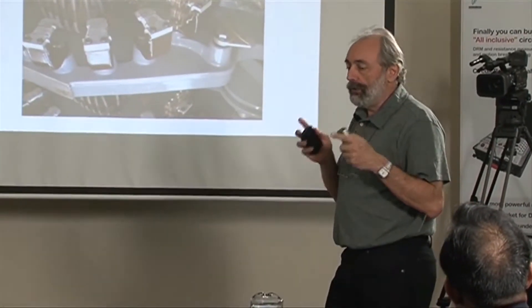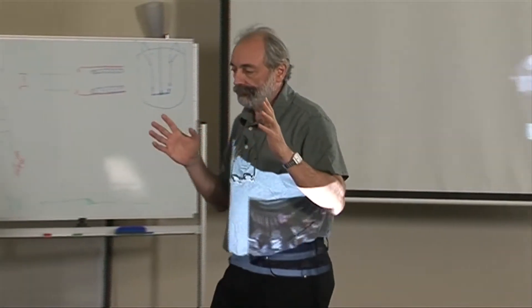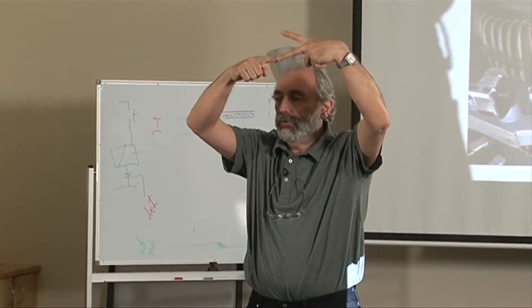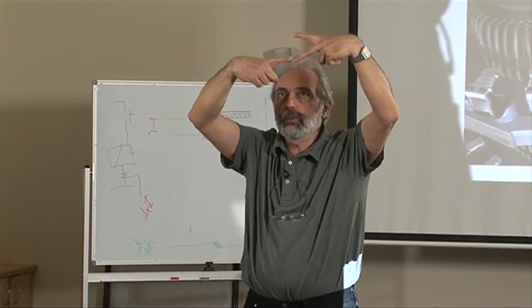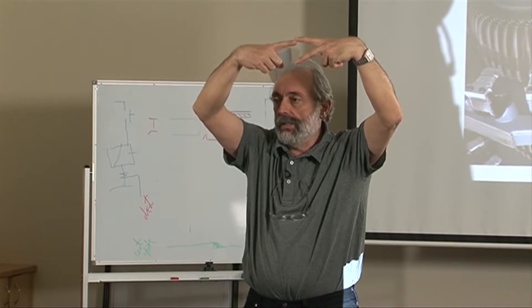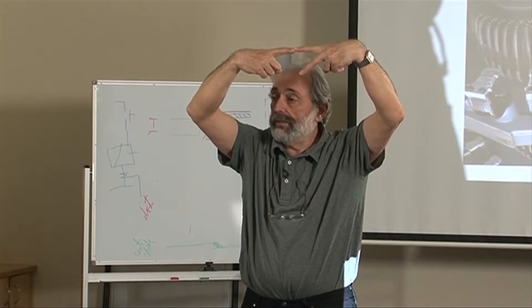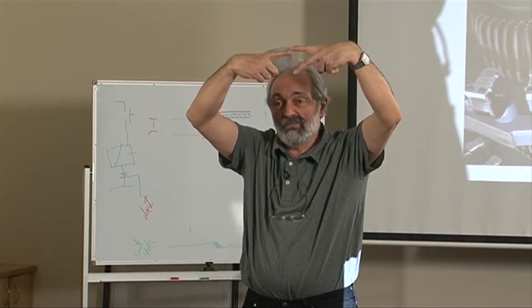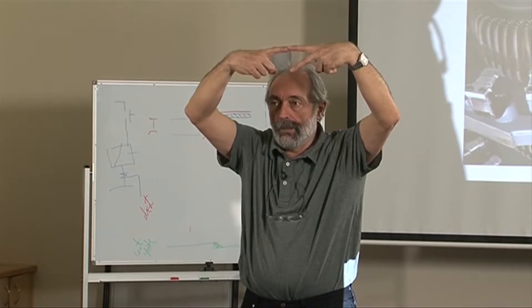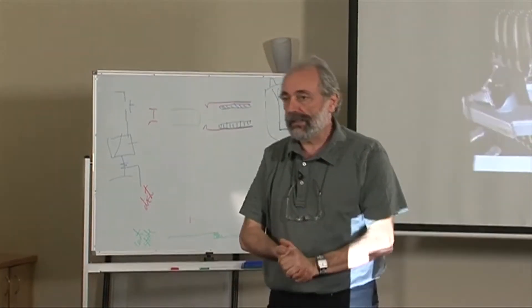So when you do a tap changing process you need to go from position 1 to position 2. So if you had your contact on position 1 and you just say let's go to position 2, what you do is you open the circuit. And on load tap changer means that the transformer has to carry a full load. So if it opens it's not going to work. So how do you change from one position to another? Well the smart guy was Dr. Jansen who patented the process. It was called the Jansen switch for many years in 1927.